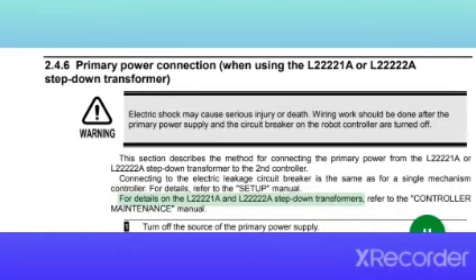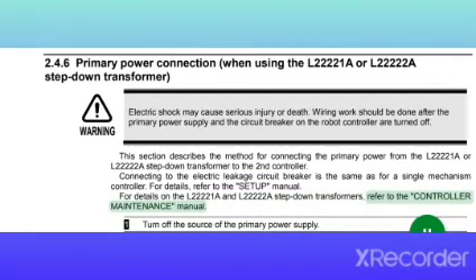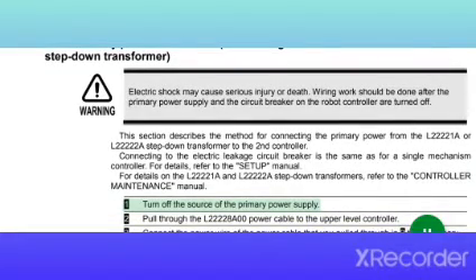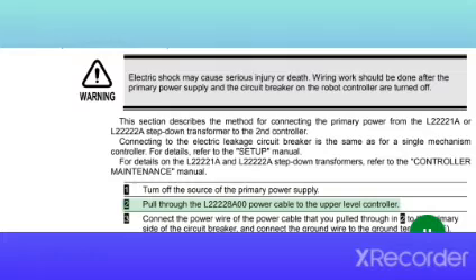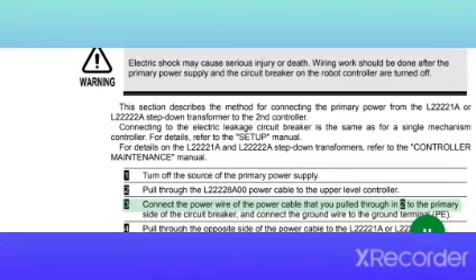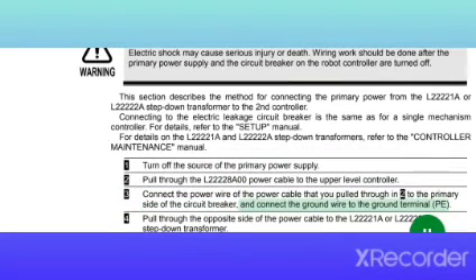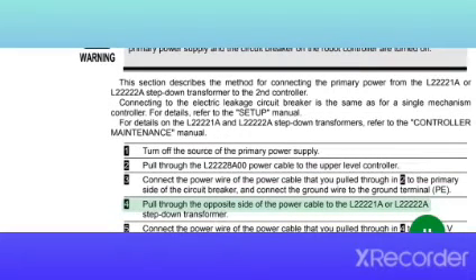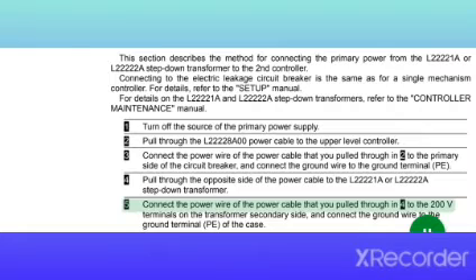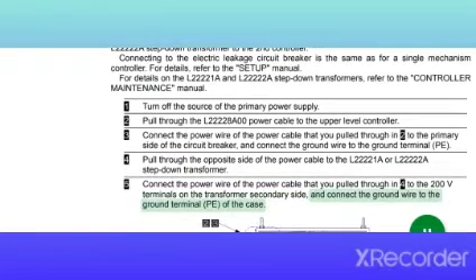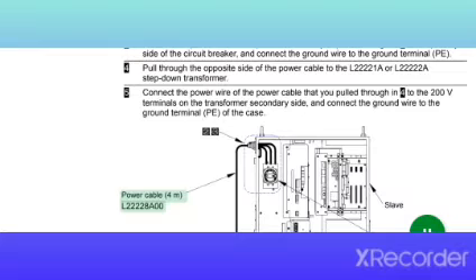For details on the L22221A and L22222A step-down transformers, refer to the controller maintenance manual. 1. Turn off the source of the primary power supply. 2. Pull through the L22228A00 power cable to the upper level controller. 3. Connect the power wire of the power cable that you pulled through to the primary side of the circuit breaker, and connect the ground wire to the ground terminal PE. 4. Pull through the opposite side of the power cable to the L22221A or L22222A step-down transformer. 5. Connect the power wire of the power cable that you pulled through in 4 to the 200 volts V terminals on the transformer secondary side, and connect the ground wire to the ground terminal PE of the case. 4 meters.